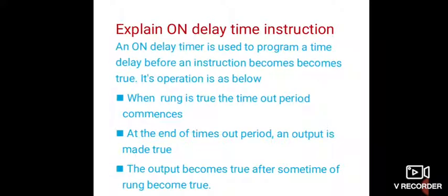Next question: explain the on-delay timer instruction. An on-delay timer instruction is used to program a time delay before an instruction becomes true. When the rung becomes true, the timeout period commences, and at the end of the timeout period an output is made true. For example, if the input becomes true, then after some time the output is to be activated. This instruction is used when we need to include a time delay between the activation of the input and the activation of the output.